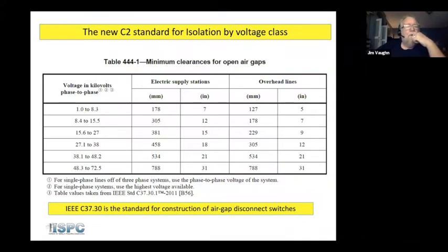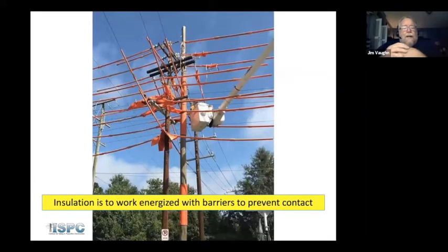Now, here's a table that I told you about, 444-1. That's out of the standard IEEE C37. And this is those open gaps that are required in order to create isolation. And you see here in a substation, it's 7 inches, and out on the line, it's 5 inches. And that's well within the gap that's created by an open dropout switch. So that is considered isolation. Now, you see in the bottom, insulation is to work energized with barriers to prevent contact.